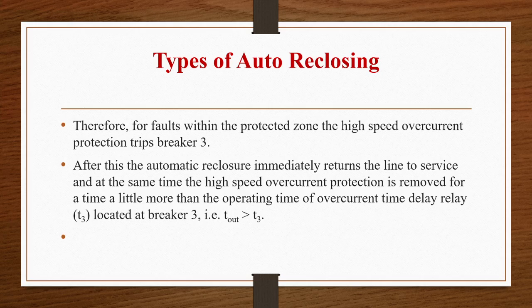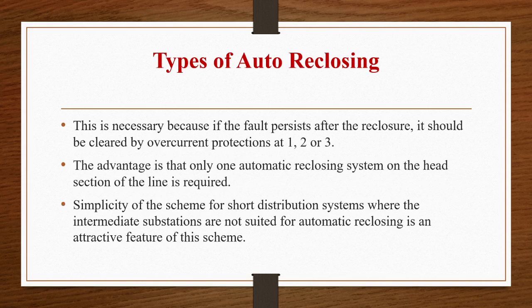So what does that mean? That T out is greater than T3. So whenever this automatic reclosure returns the line to service and at the same time the high speed overcurrent protection is removed for a time which is a little more than the operating time of the overcurrent time delay relay T3, located at breaker 3, that is, T out is greater than T3. This is necessary because if the fault persists after the reclosure, it should be cleared by overcurrent protections at 1, 2 or 3. The advantage is that only one automatic reclosing system on the head section of the line is required.